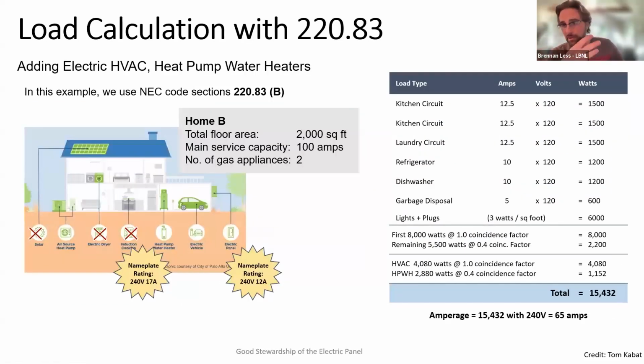The alternative is this sort of bottom-up nameplate rating, 220.83. This looks more like a spreadsheet. You're going to tabulate the loads that are in the home, add them up, apply an adjustment factor, and you get your load at the end. So two very different approaches. This one gives more of an asset rating, the previous gives more of an operational rating. Let's jump to our next slide.